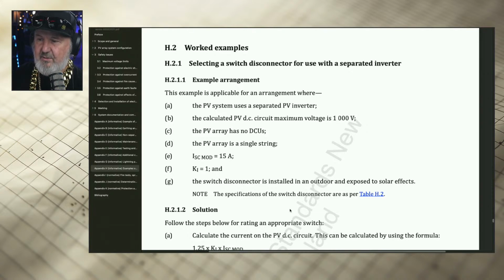Okay, so in this arrangement, we are selecting a switch disconnector with a separated inverter, so emphasis on separated, i.e. galvanically separated, i.e. you probably can't even buy one anymore. So this is kind of old school now. And in this example, the PV array is connected to the inverter. The maximum voltage under temperature compensated conditions is 1,000 volts.